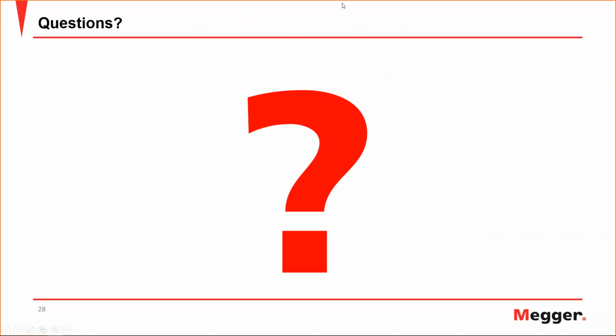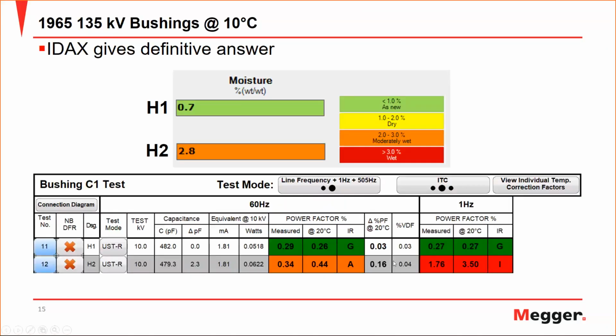We have some questions, starting with the first question: whether LF, I believe he means line frequency, or 1 hertz test can detect bushing insulation degradation due to any electrical stress, but not due to moisture contamination. So when we look at 1 hertz, we are not able to tell the exact change that has happened. We just know that there is a change that took place, and you will need to do an IDAX in order to determine the moisture and the oil conductivity.